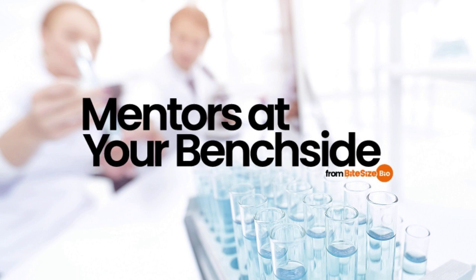Number 2. Calibrate your pH meter often. You calibrate the spectrophotometer each time you measure the optical density of a microbial culture using a blank. You calibrate a spectrophotometer before every measurement, in fact. The same should be done with a pH meter. Calibrating a pH meter is done using calibration solutions that have an accurately known pH. The process should be performed every time you use the instrument, or at least every morning that the pH meter will be used.